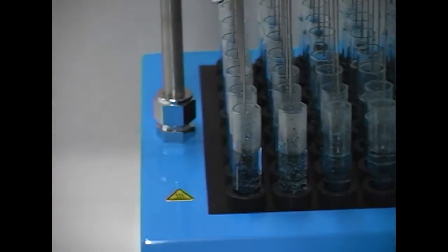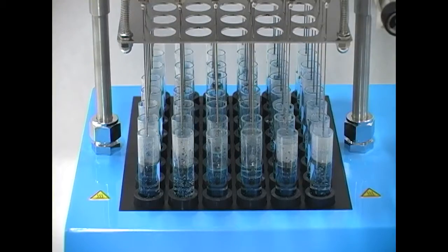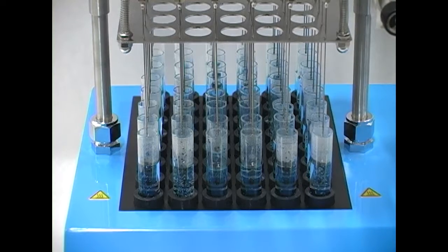The 48 position multivap comes with a heated aluminum dry block which provides reliable uniform heat up to 120 degrees Celsius.